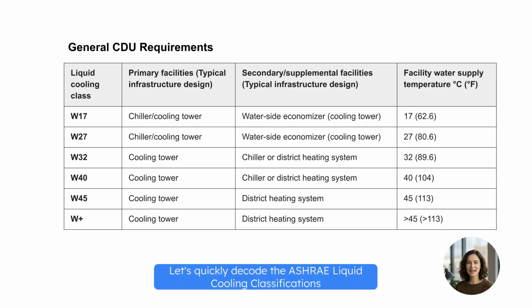Let's quickly decode the ASHRAE liquid cooling classifications and what they mean for our infrastructure design. Start at the top with W17 and W27. You'll see the supply temperatures are tight, 17 and 27 degrees Celsius. To hit these targets, the table shows our primary facility is the chiller. We are still reliant on mechanical compression here, which keeps our PUE, power usage effectiveness, higher.